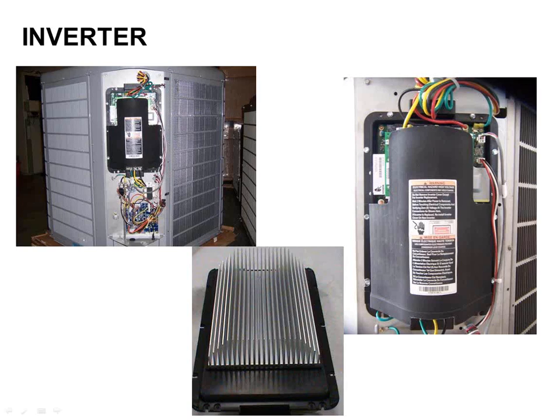An inverter, for the newbies, is the same thing as a VFD, right? So if we were doing a commercial job with a fan or a pump, we would have called it a VFD. Here we're calling it an inverter. A VFD is an inverter, right? So I take the power in, I modulate the signal, and then I control the frequency of it coming back out. This is what an inverter might look like. So in this case, it's a single-phase piece of equipment. So I have 230 volts single phase coming in.